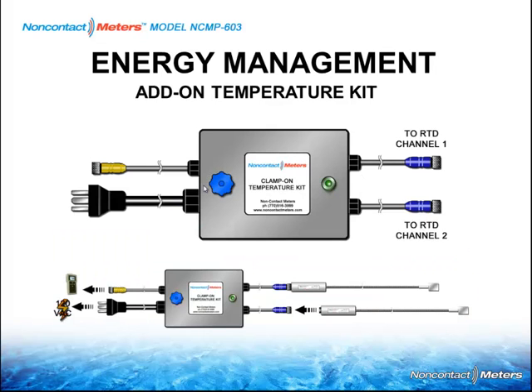And here's a picture of the technology. It's basically an interface that's going to have two strap-on RTDs, and we can do temperature with strap-on RTDs. We're not looking for the actual temperature, we're looking for the differential between these two temperature sensors. So there are some rules on how to mount them on the pipe. It works great on metal applications for BTU, not so much on a plastic pipe application. You don't usually do BTU with plastic anyway. It does require a power supply for operation.